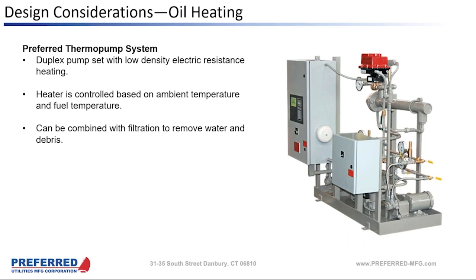There's really two ways these are controlled. There'll be an ambient temperature sensor that senses the air temperature. And when the air temperature drops below an adjustable set point, then it kicks on the lead pump. And if the oil going through the heater is colder than the set point on that heater, then the heater comes on and warms up that oil. And typically we will size the heaters for a 40 degree F temperature difference between incoming and outgoing. And 40 degrees F is a lot. So it's a nice, comfortable margin.